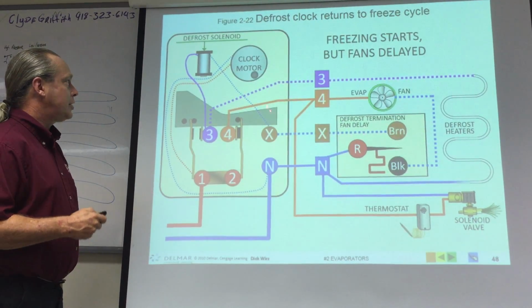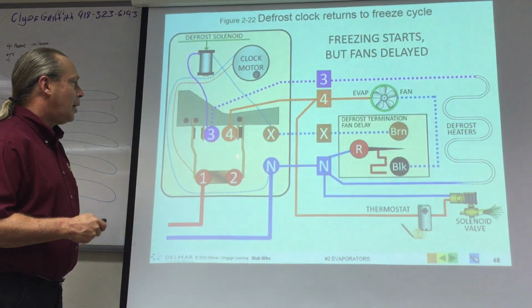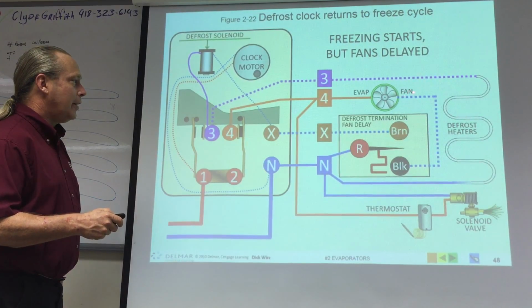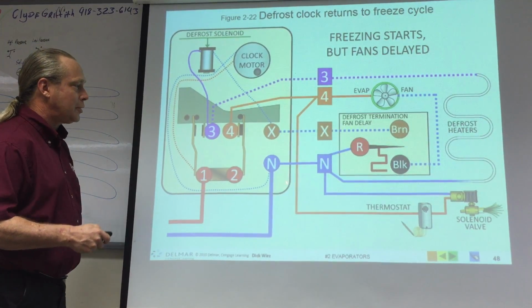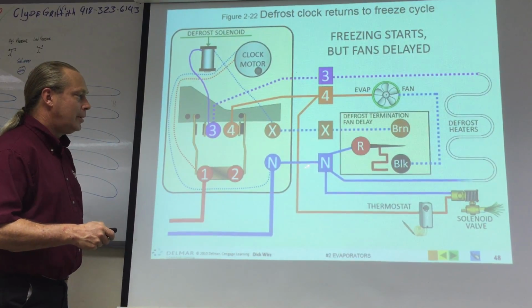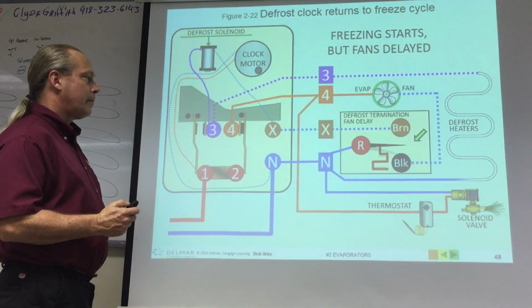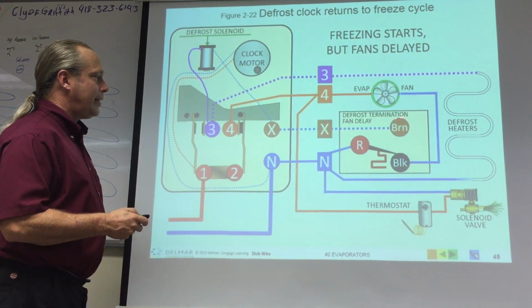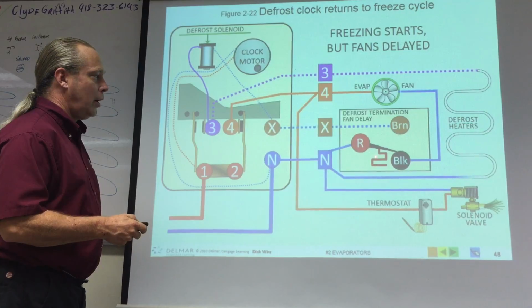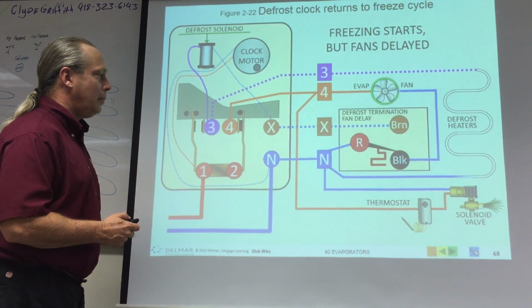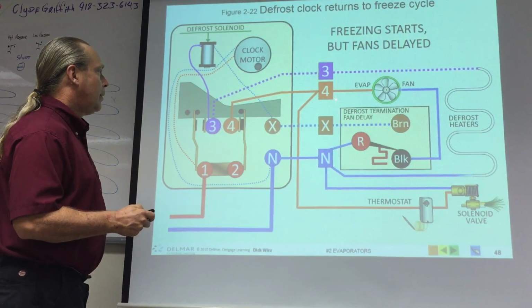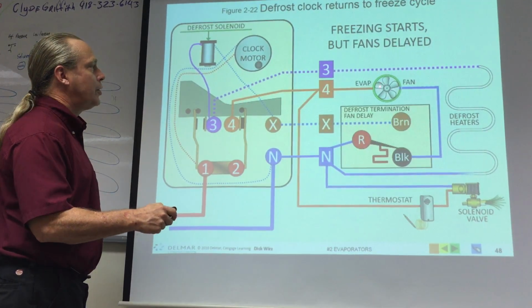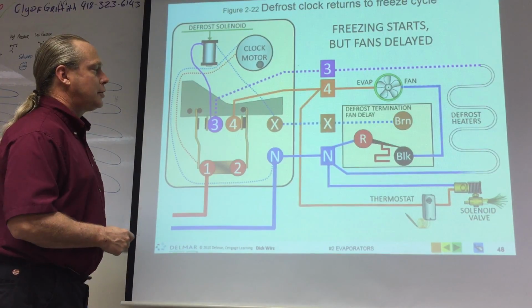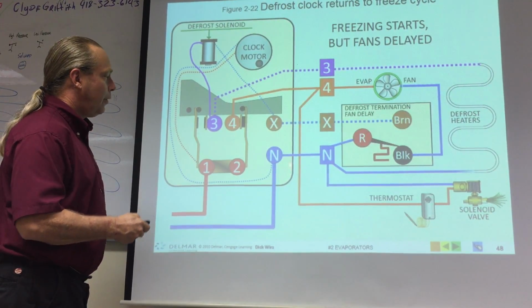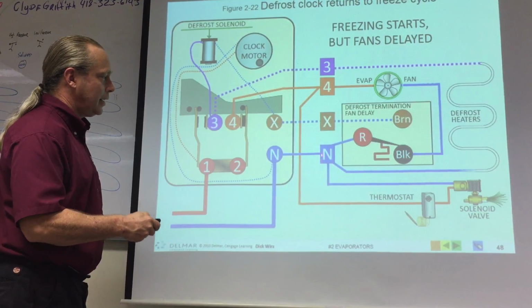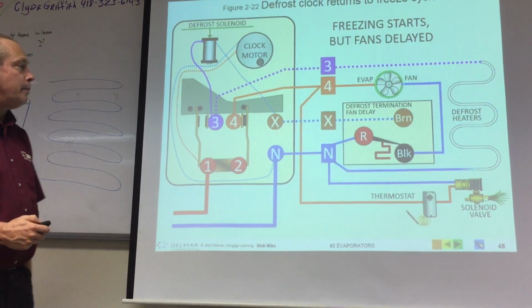And here we go. We have lost connection to the solenoid. Our power is going through the evaporator fan, but it can't do anything else. But we still have the compressor running. Now that this bimetal coil has shrunk enough to allow power back to the black terminal, power can go through to 4 to the evaporator fan and circulate the air, while from 4 through the thermostat and solenoid are keeping the compressor on.